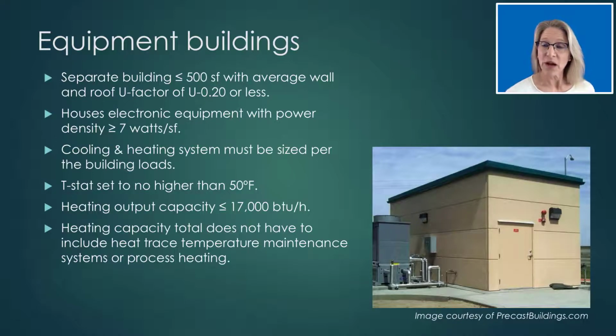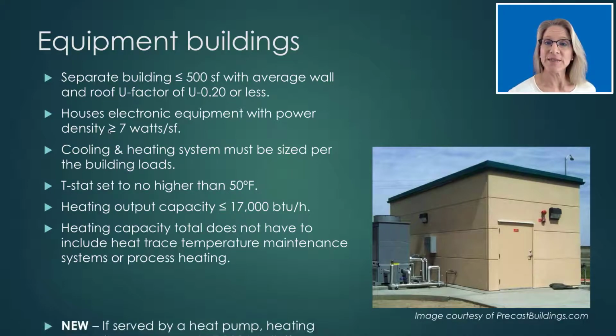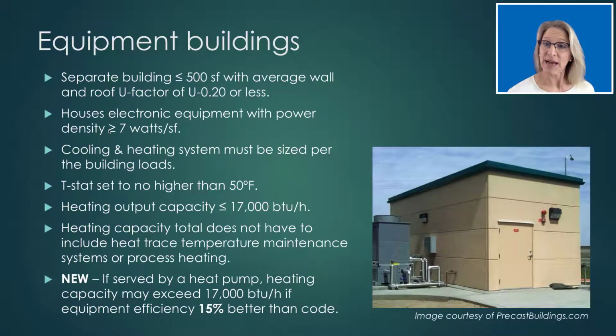So to solve this problem, an exception has been added that allows the heating capacity of the heat pump to exceed 17,000 BTUs as long as the equipment efficiency is 15% better than the code minimum required efficiency for that heat pump.